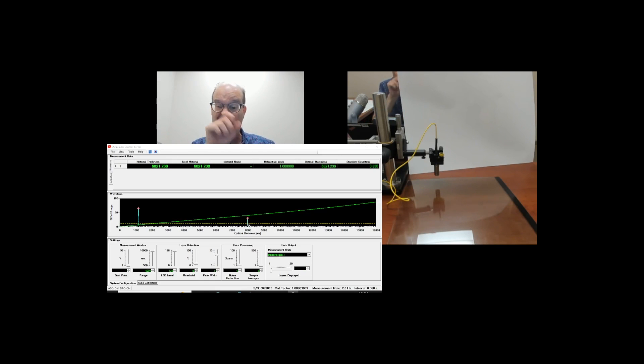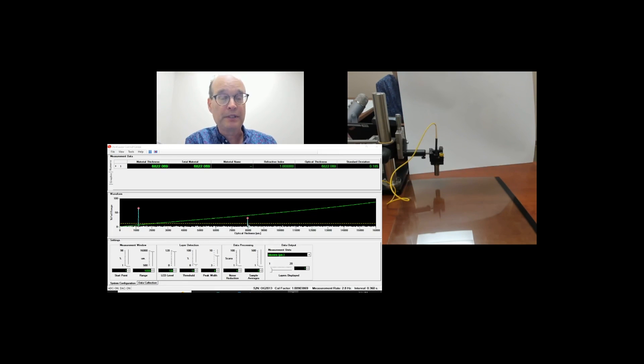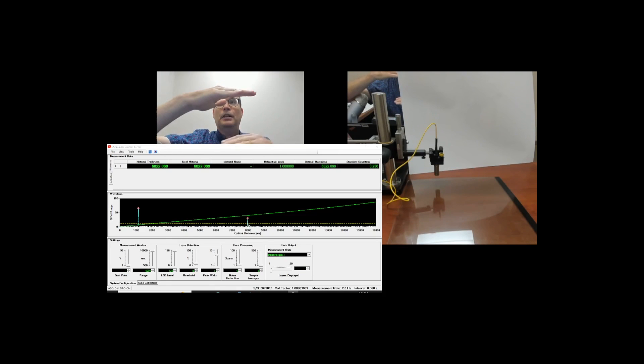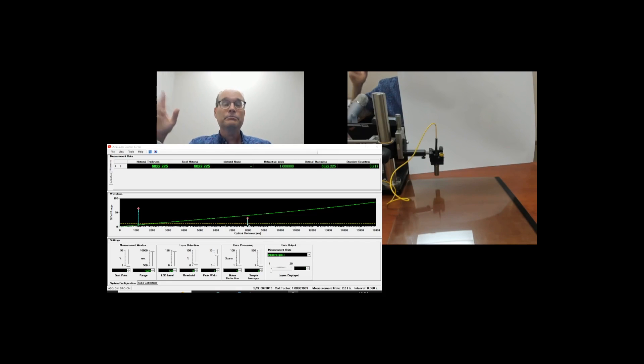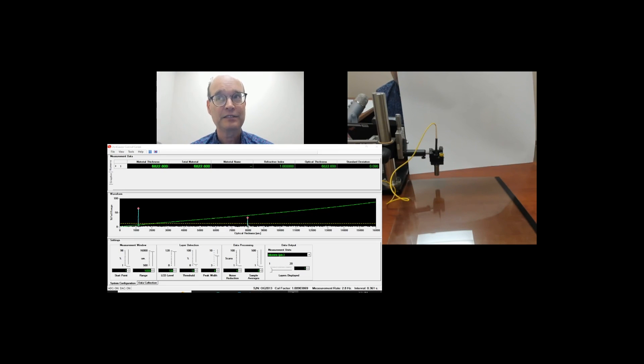That poses an interesting problem for us in particular, because normally we don't care what the distance is between the probe — the face of the probe — and the first surface that we're measuring. We're usually measuring the first surface and the surface below. But sometimes you do want to know how far the probe is from the first surface. Fortunately, we have a solution for that — it's called a reference signal generator.